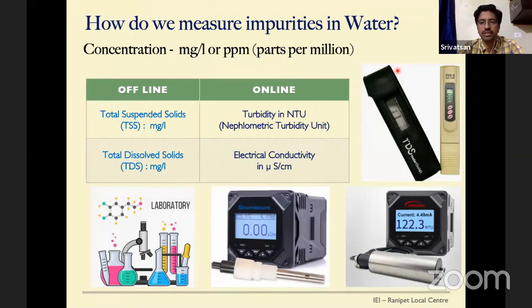Total dissolved solids is measured in the laboratory using gravimetric analysis. You evaporate the water, so the impurities stay behind while the water is taken out. Whatever leftover salts are present in the water show the dissolved solids. Of course, you first need to filter it to be free from the suspended particles to measure the dissolved solids content. These processes in the laboratory usually take time to measure individual ions.